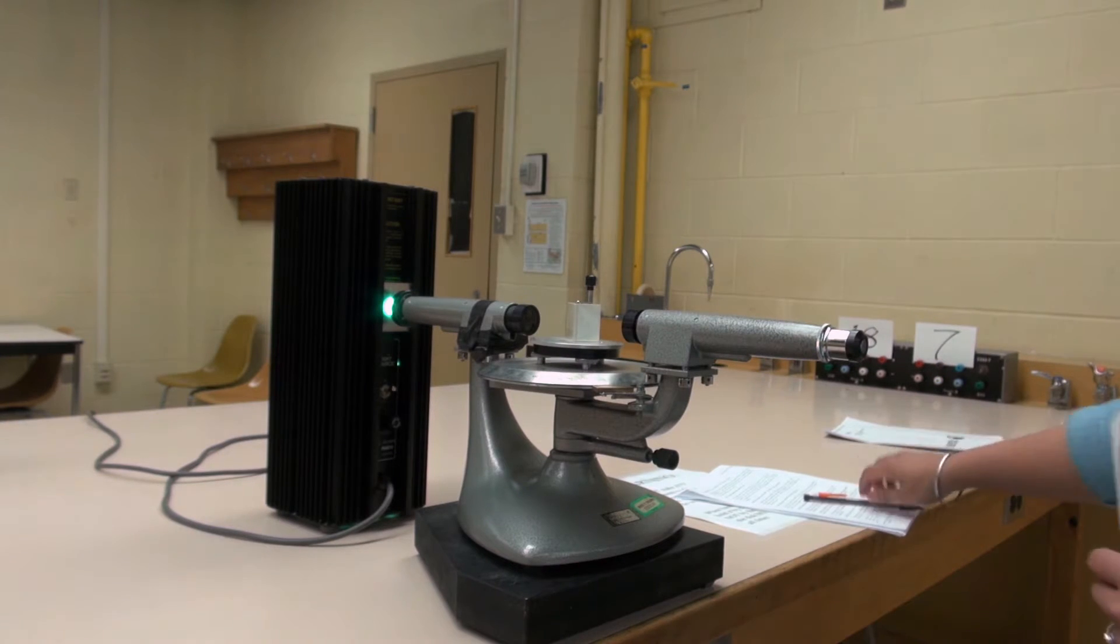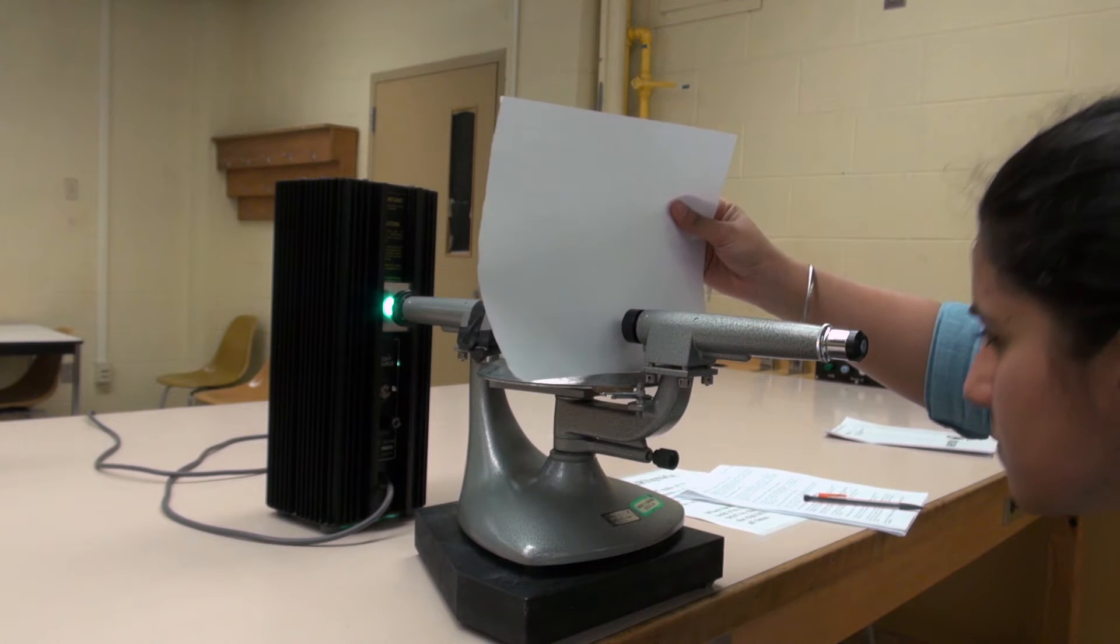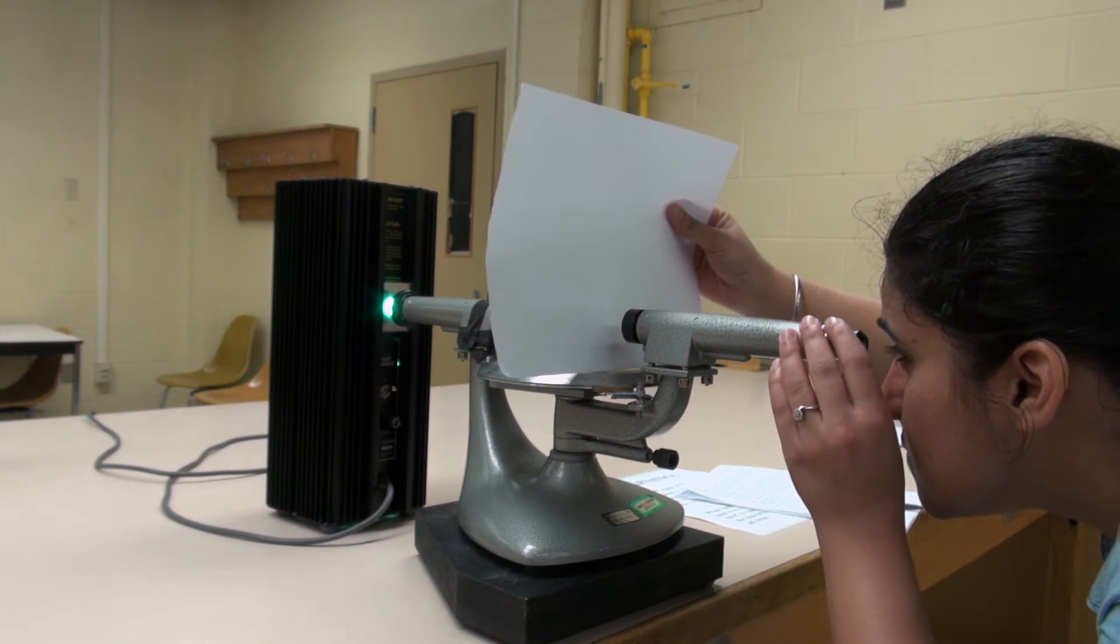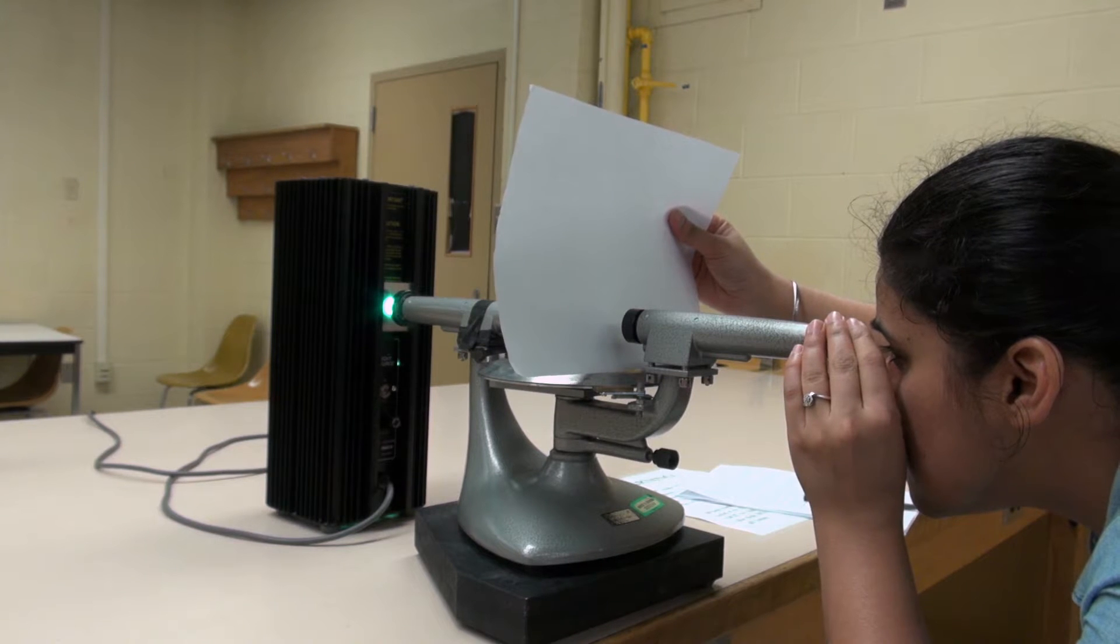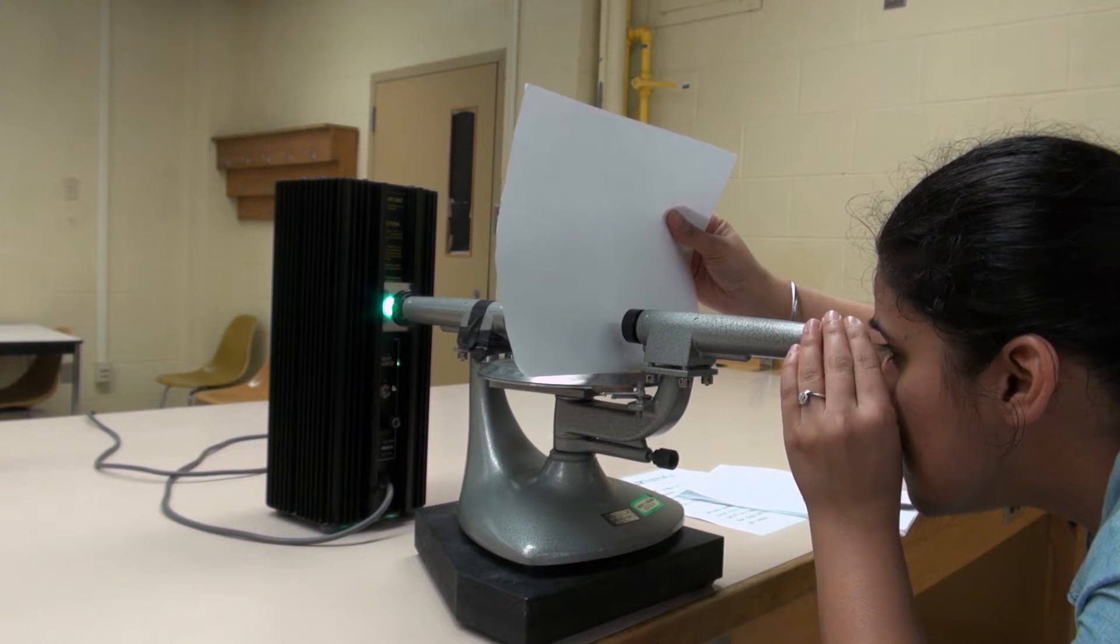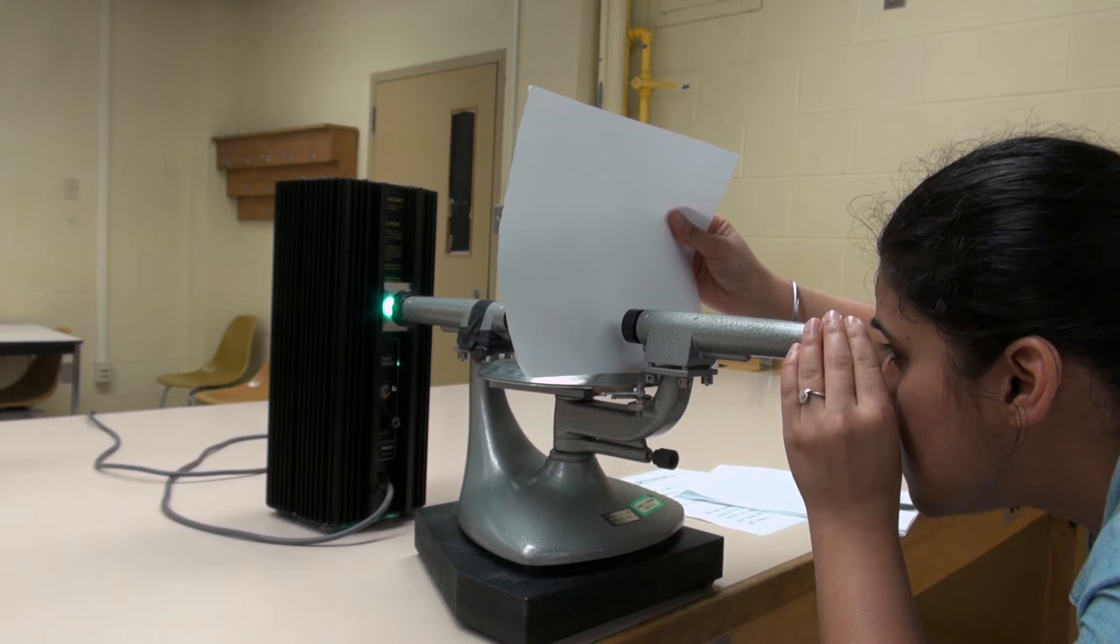Carefully place a sheet of white paper in front of the prism. Look through the telescope and observe the crosshairs. By sliding the eyepiece lens in and out, adjust its position until the crosshairs are in sharp focus.